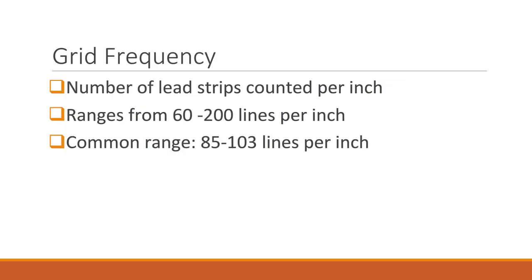Another term to be familiar with is grid frequency. Grid frequency is the number of lead strips counted per inch and ranges from 60 to 200 lines per inch. The common range that we see in the clinical setting ranges from 85 to 103 lines per inch. Both the grid ratio and the grid frequency are often listed on the grid label.